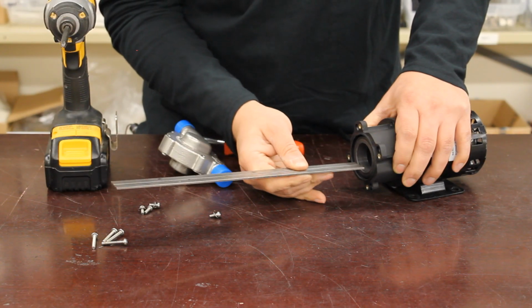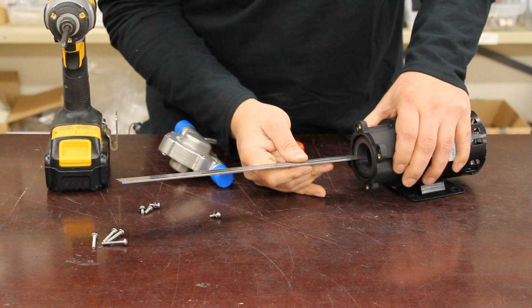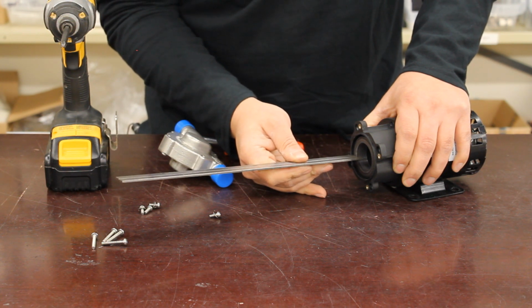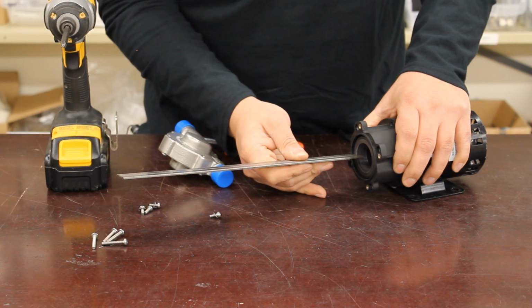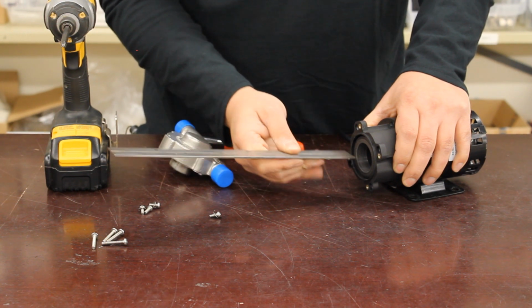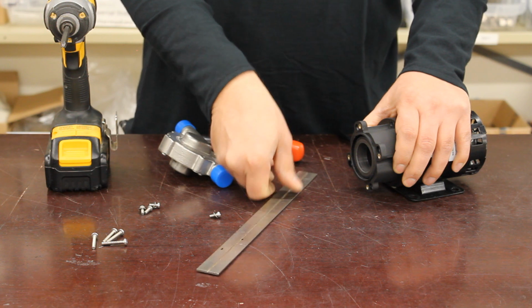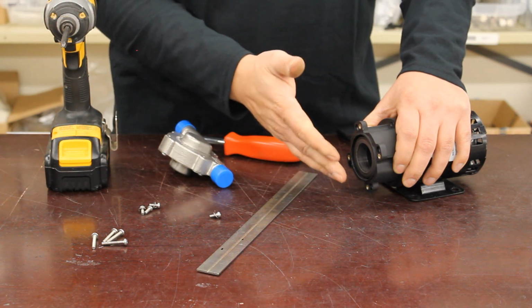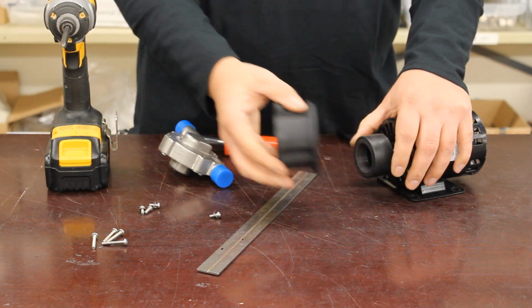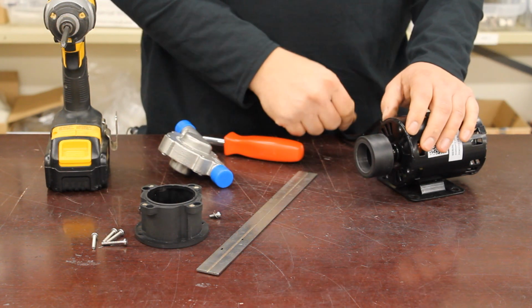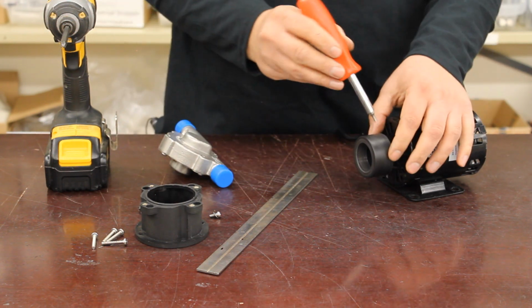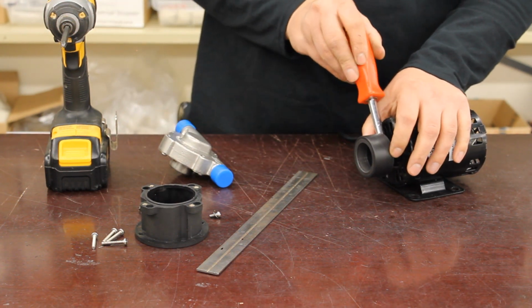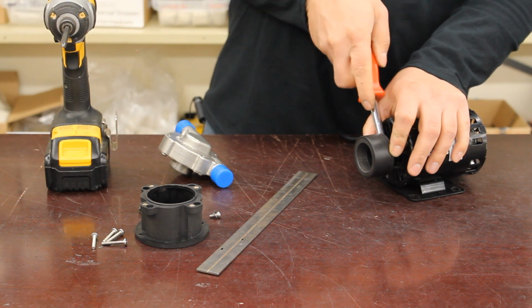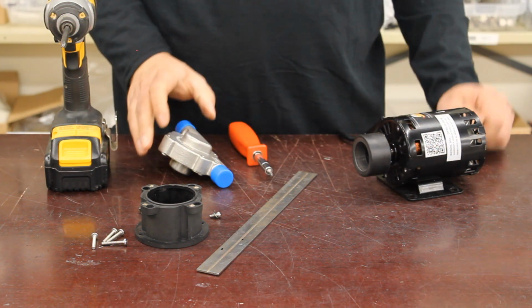Use a ruler that's generally accurate and verify that the cup magnet is only set back a max of 1/8 of an inch, if not a touch less. So you can verify the depth and then use your set screw to reposition the cup magnet, and make sure that you tighten it really well before you put the pump back together.